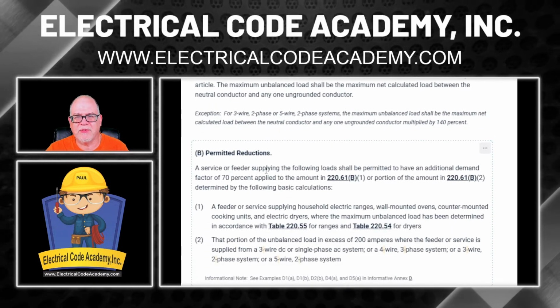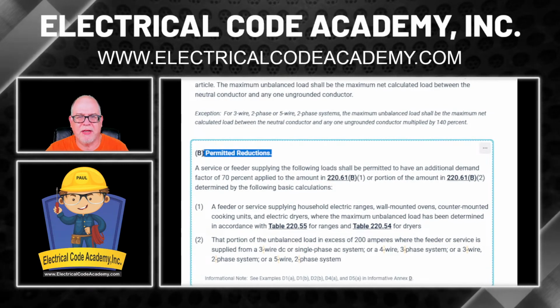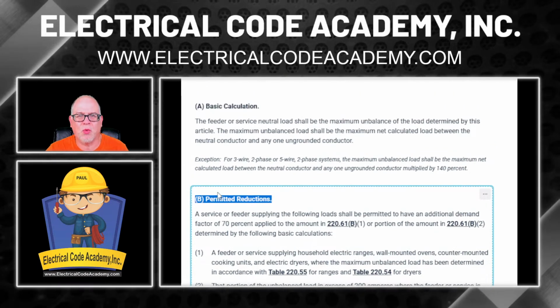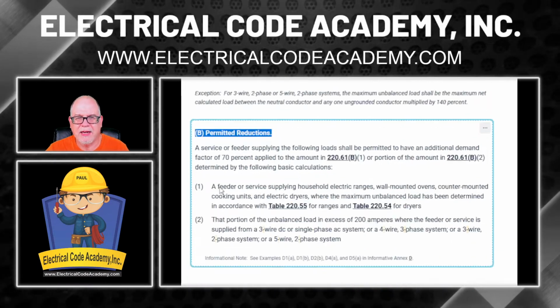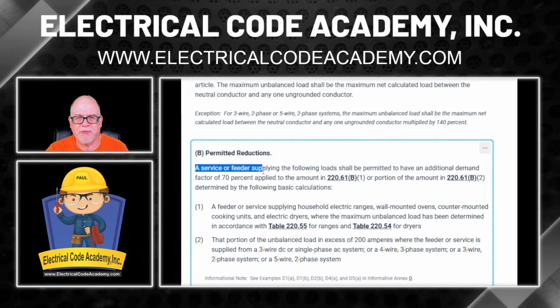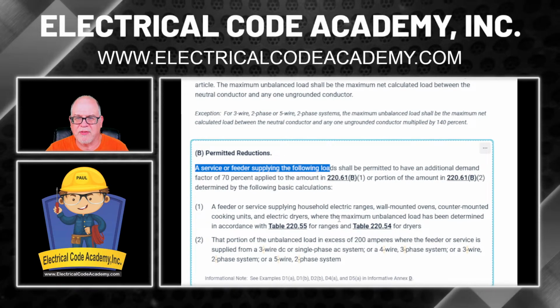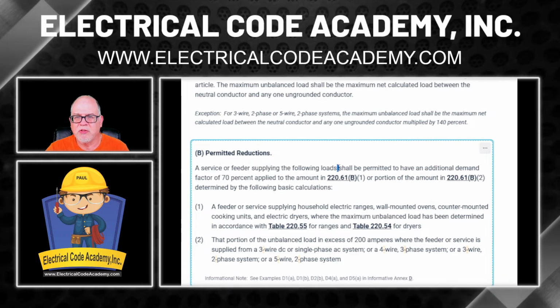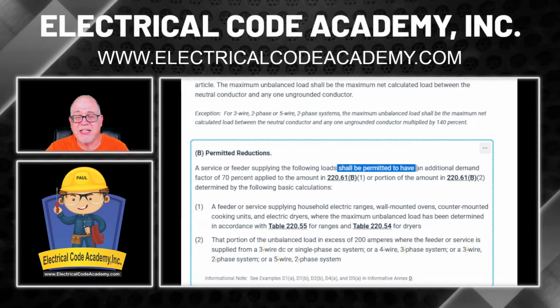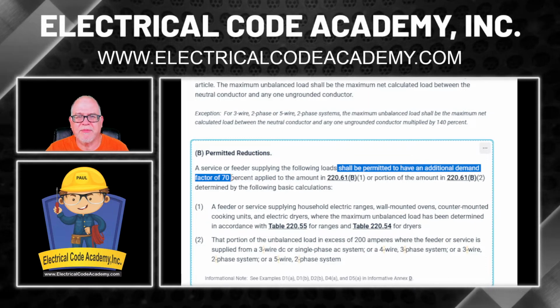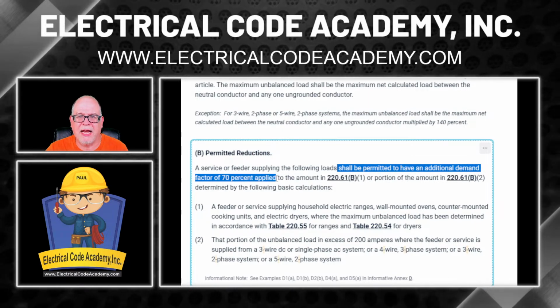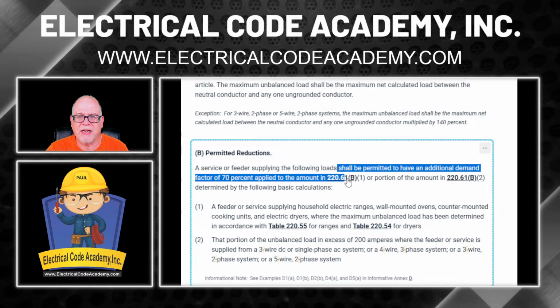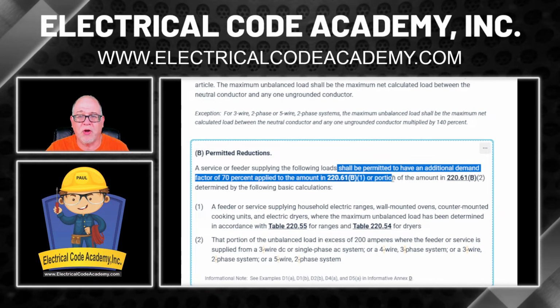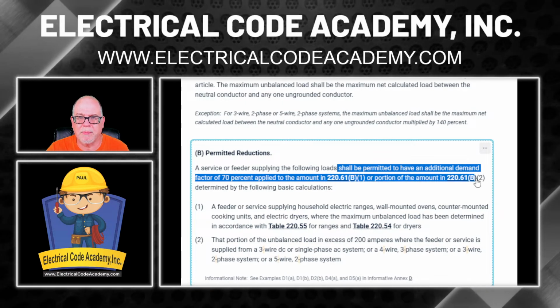And we're going to look and see if we get what's called a permitted reduction. So it's 220.61(B). And here's what it says. It says a service or feeder supplying the following loads, that's these loads right here, shall be permitted to have an additional demand factor of 70% applied to the amount in 220.61(B)(1) or a portion of the amount in 220.61(B)(2).